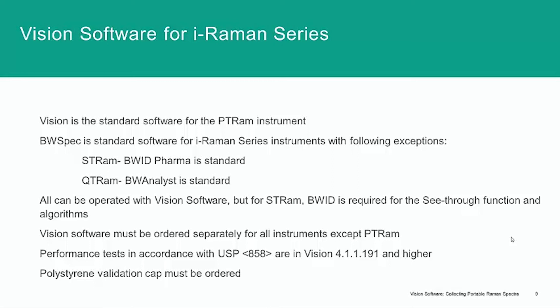So, please be sure to order your vision software separately for your other instruments, and keep in mind that the vision software includes the full performance tests in accordance with the USP-858. And in order to run those, the polystyrene validation cap is also needed.